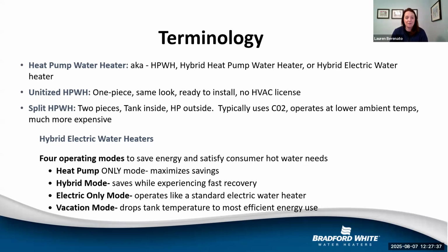One of the biggest pieces of feedback we get is that engineers are used to having a design where you have your low boy water heater and then your air handler unit above it. You cannot do that with a heat pump because the heat pump will take up that entire space. So it's really changing the way you design maintenance rooms. When you are designing maintenance and facilities rooms, and when you are designing for mixed use residential, the biggest moneymaker for you is space. So now we're taking more space that's not livable space, because it's your utility closet. So that has been a challenge for designers.